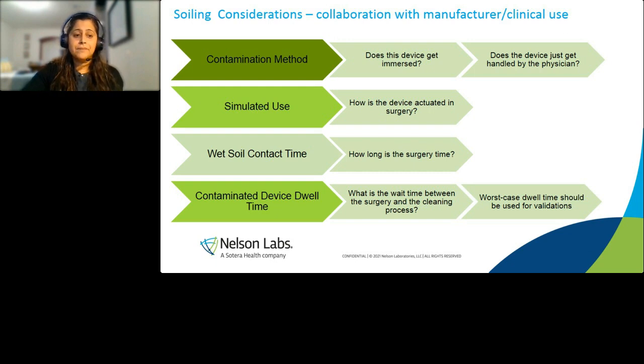And simulated use, where we're figuring out how long this device is used. Is it 15 minutes, 20 minutes? So we know what the time is for soiling. What is the wet contact time? How long is this device used in the surgery? And then the dwell time. We're always looking at the dwell time, right? Once the device is done, it's put on the side. How long is that device sitting before it goes to central processing for cleaning? That is also considered in the validation.